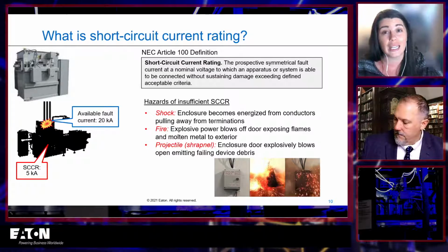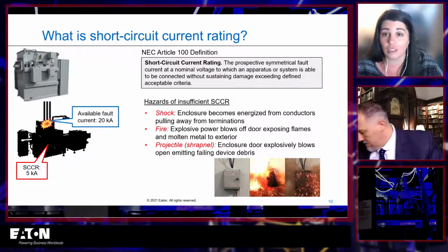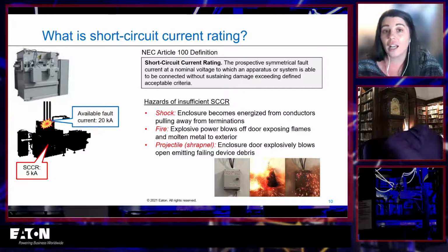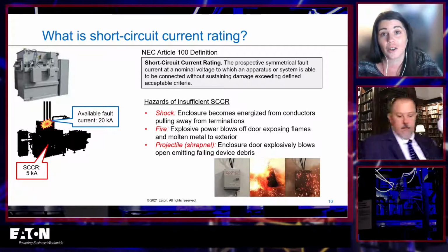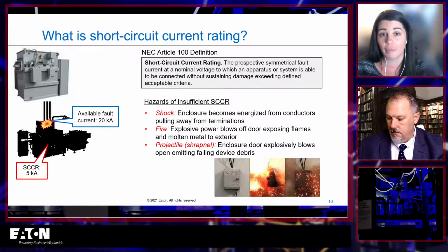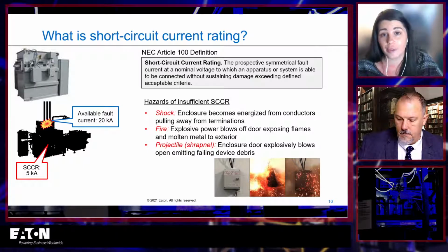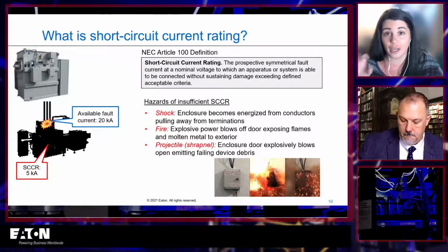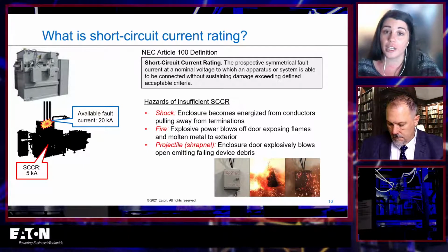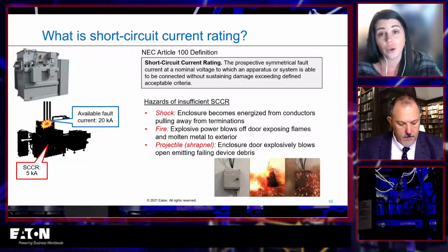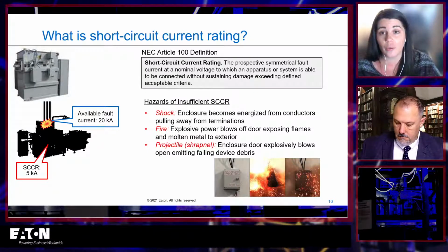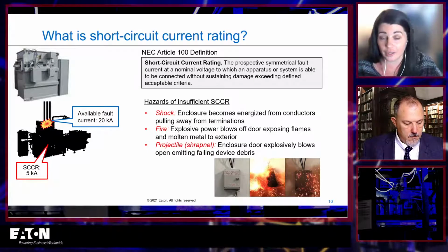If you want to be able to use it again after a short circuit, it's something called type 2 protection. Not the same thing as short circuit current rating. It's an extra level of protection on top of that. And then the final one, projectile hazard, that's usually pretty obvious, right? Shrapnel, pieces of debris flying all over. So if I don't have enough SCCR, I will create one or more of those hazards.